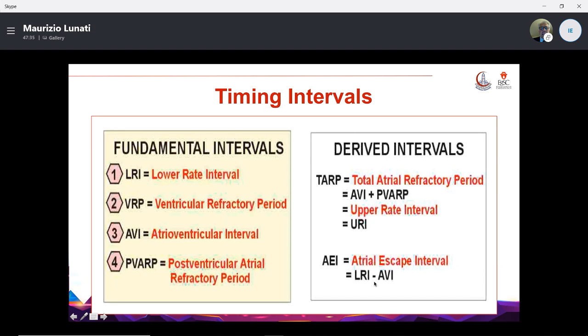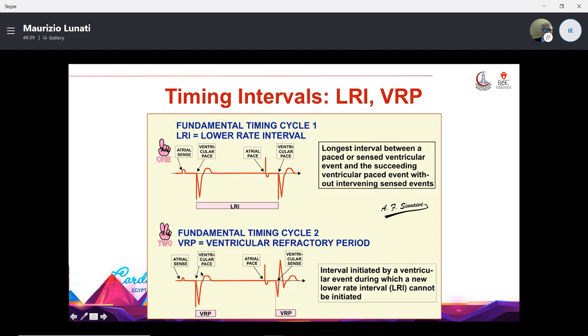So, fundamental timing cycle 1: the lower rate interval. The lower rate interval is the longest interval between a paced or a sensed ventricular event and a subsequent ventricular paced event without an intervening sensed event. This is the lower rate interval, the distance between a ventricular pace and another ventricular pace. Second, the second fundamental timing cycle is the ventricular refractory period, which starts from the beginning of a ventricular event and lasts around 300 milliseconds. It is the interval initiated by a ventricular event during which a lower rate interval cannot be initiated. Nothing can be sensed in this ventricular refractory period.